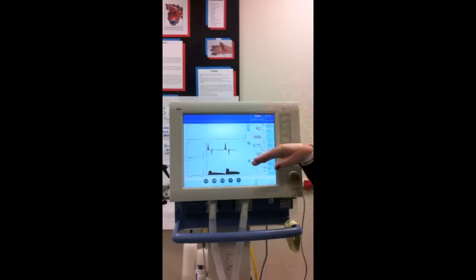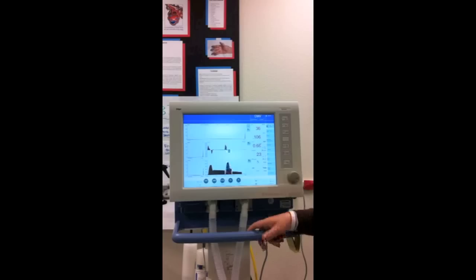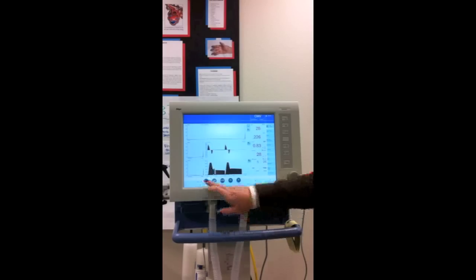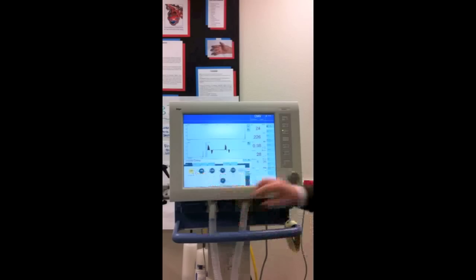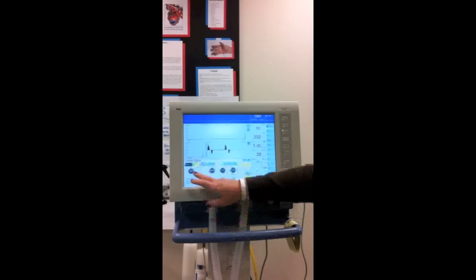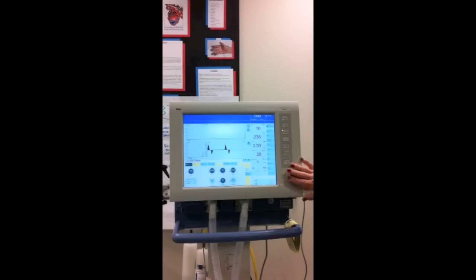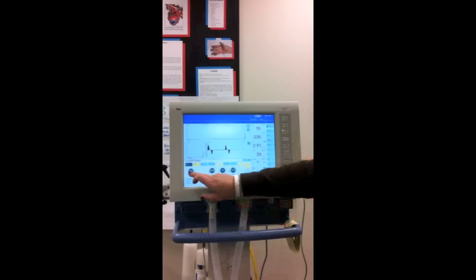Like the other vents, you got red alarms. Those are your high priority. Make sure you do something quickly if you get a red alarm. Yellow are not so priority, but of course still important. So here are some quick keys. You can make some changes. You push it. Yellow means that you can change the setting on it, the dial. And if you do not hit confirm and you go away, it will stay where it was. You must hit this button over here if that's the confirm button.